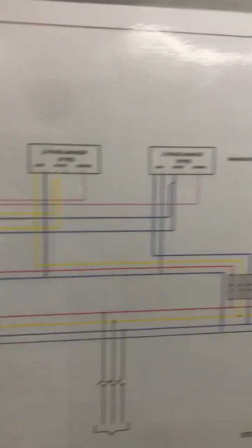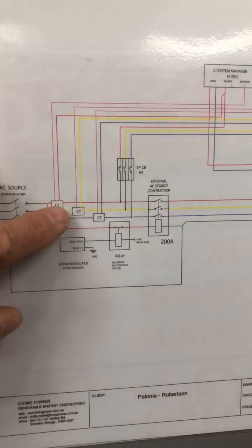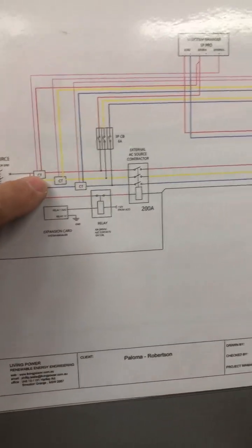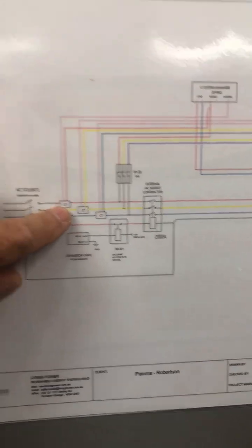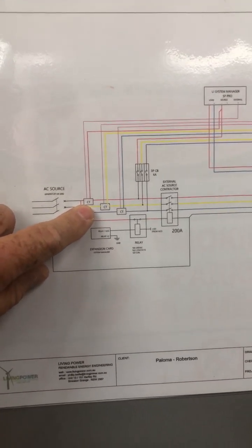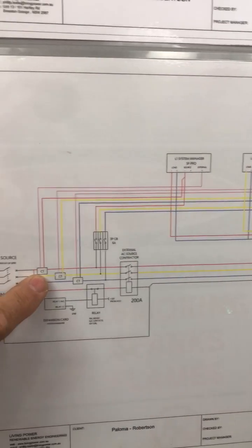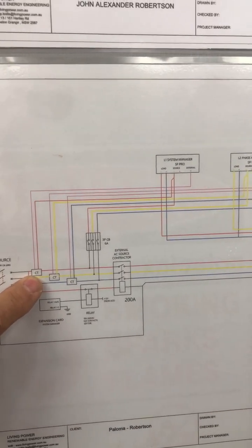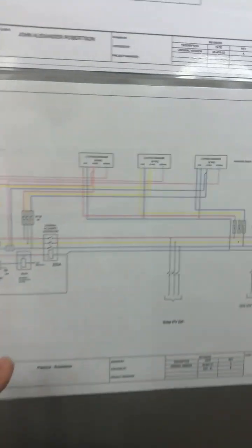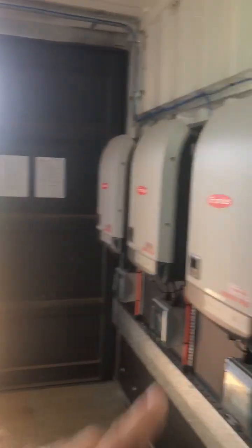Then we also have our controls. We've coloured those just to make it a little easier to understand when you're here on site. So we have CTs, current transformers, measuring the current coming from the generator, and also sensing any backflow. If there's any backflow coming from the solar array and trying to find its way back into the windings on the generator, the Selectronic inverters, which are our multi-mode inverters, would actually ramp these down so that we don't have backflow issues.